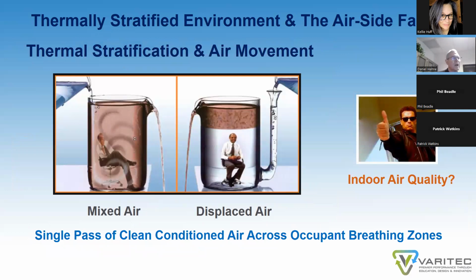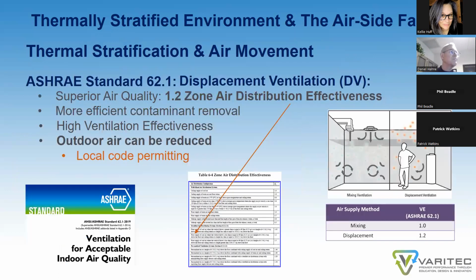Consequently, a thermally stratified environment promotes clean, cool, conditioned air across the breathing zone, as opposed to a mixed air system, which is doing its job: should somebody be sick in a room and they cough or sneeze or even tidal breathing, they will eject virally loaded droplets within the space. The mixed air system is doing its job by thoroughly mixing that contaminant throughout the space. A thermally stratified environment discourages to some extent that phenomenon, allowing for better IAQ and can reduce the risk of infection. ASHRAE recognizes better IAQ for buildings that use displacement ventilation.